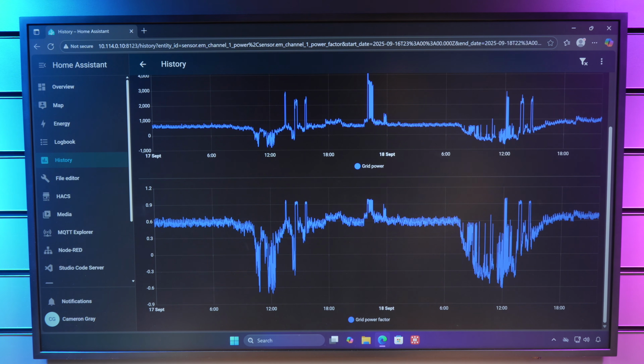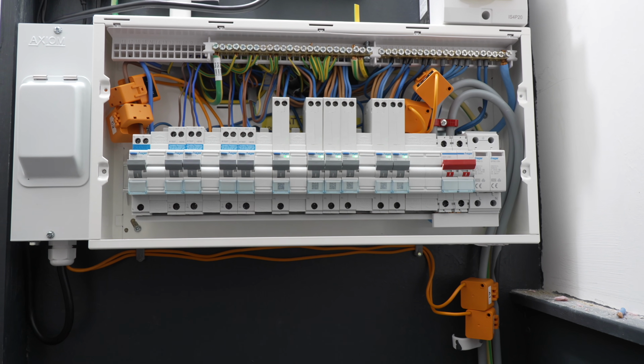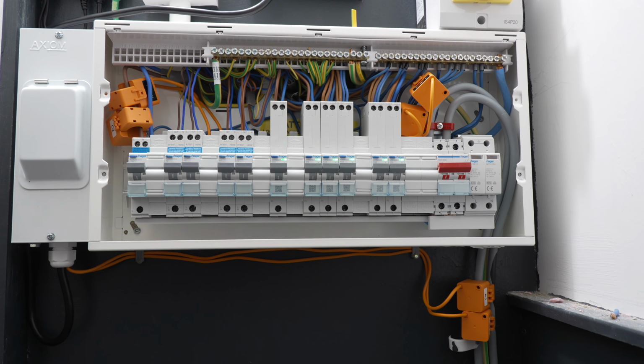As we talked about before, the issue seems to be where you have two different CTs on the same letter of input that are getting wildly different power factors. So what I thought I would do is, instead of that, make it so that each pair of CTs on each lettered input is measuring the exact same power factor by making them all measure the same circuit as each other. So essentially, I've doubled up the CTs onto each of my circuits.